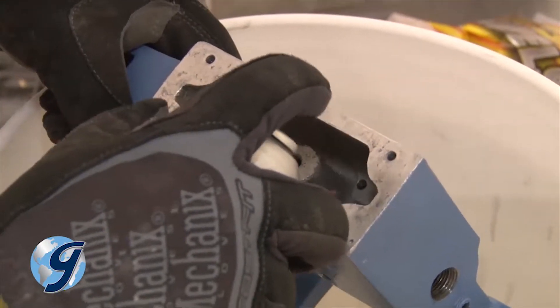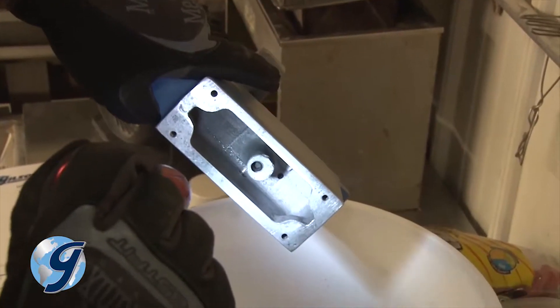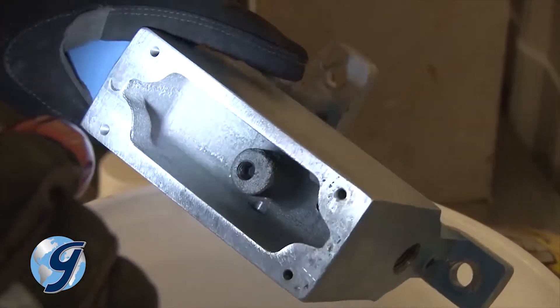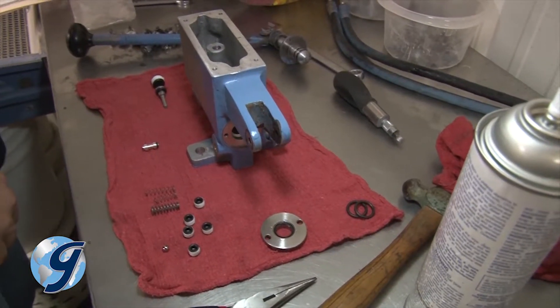Now that all appropriate components have been removed, clean all residue buildup from the pump. Next, inspect the entire pump to confirm that it is completely dry and free from dirt. Now you're ready to rebuild the pump using parts supplied from your Gilson pump repair kit number two.